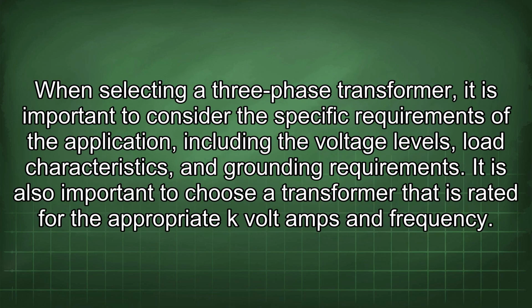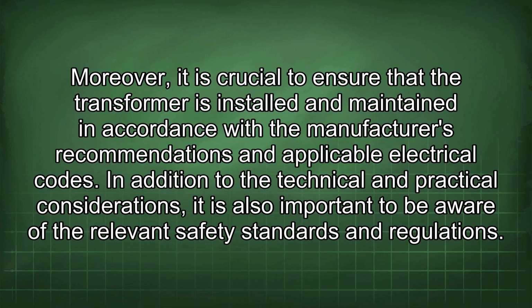When selecting a three-phase transformer, it is important to consider the specific requirements of the application, including the voltage levels, load characteristics, and grounding requirements. It is also important to choose a transformer that is rated for the appropriate kVA and frequency. Moreover, it is crucial to ensure that the transformer is installed and maintained in accordance with the manufacturer's recommendations and applicable electrical codes. In addition to the technical and practical considerations, it is also important to be aware of the relevant safety standards and regulations.